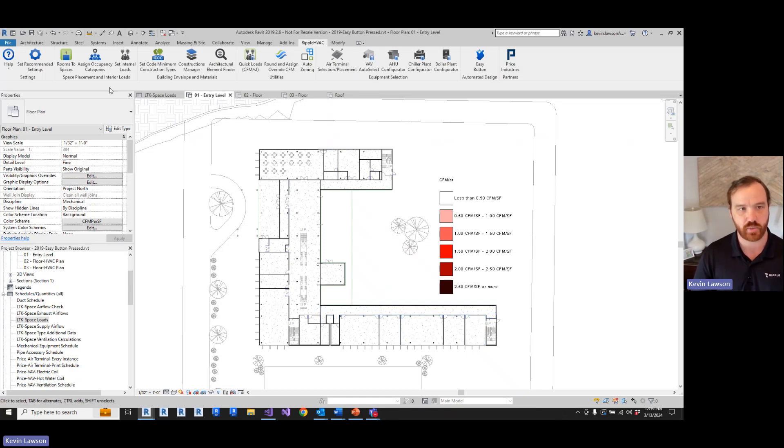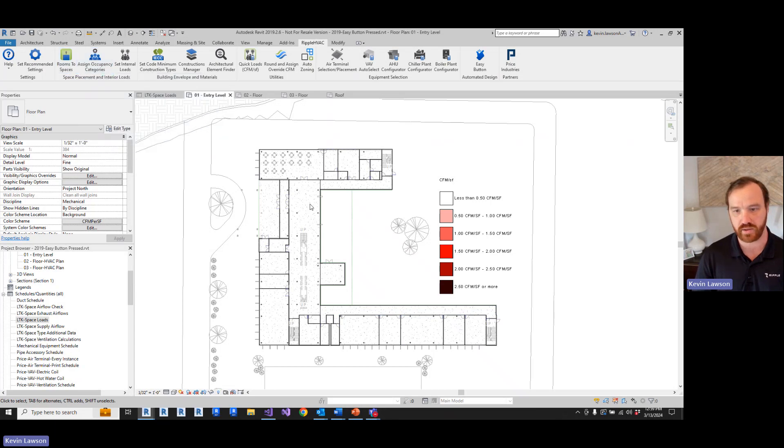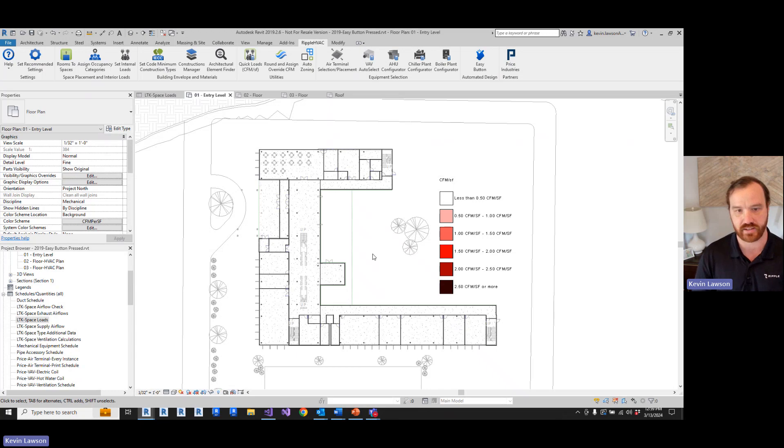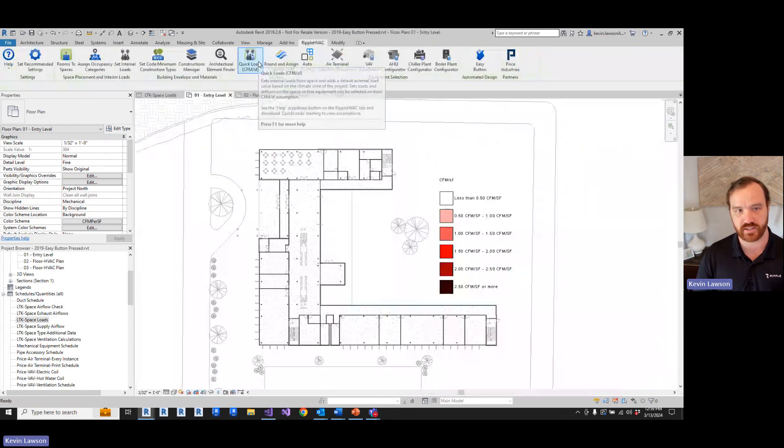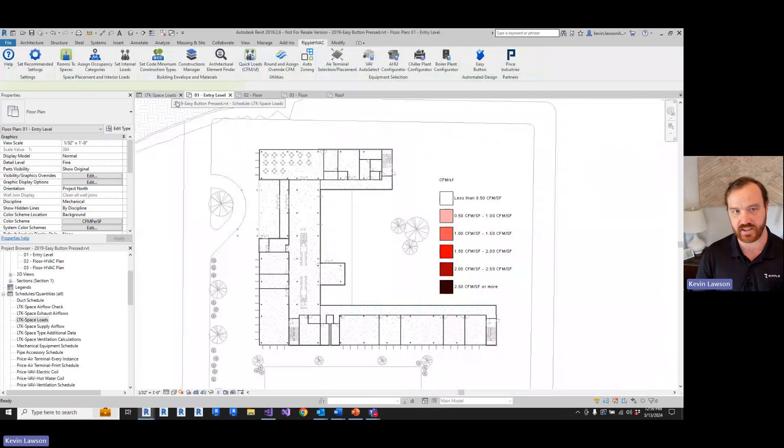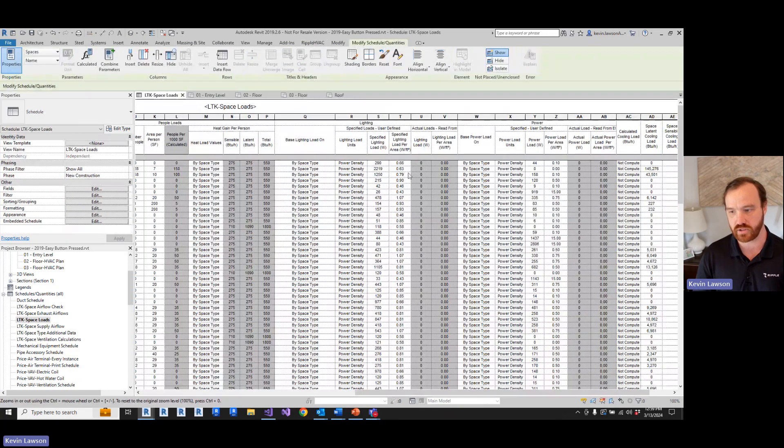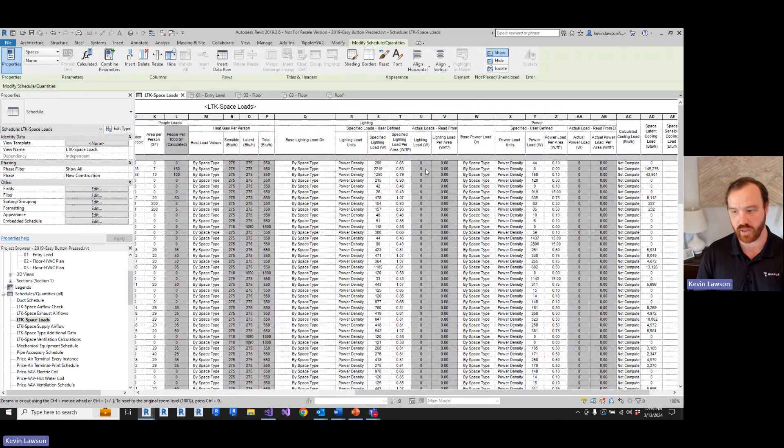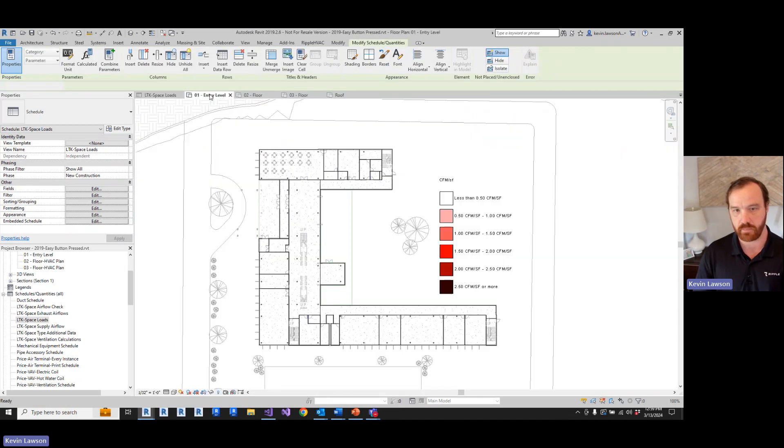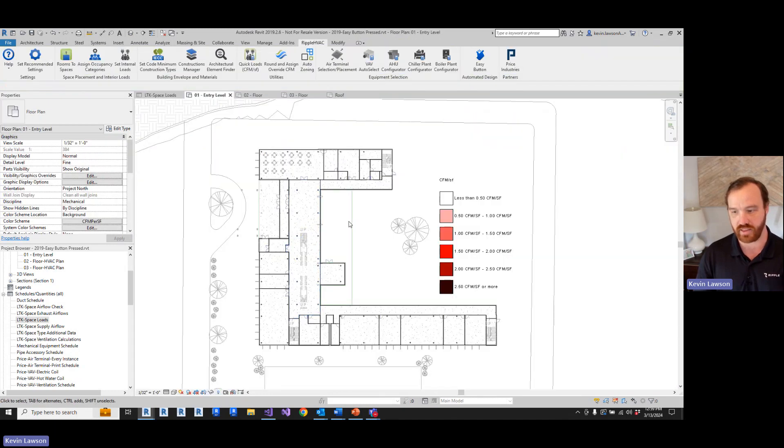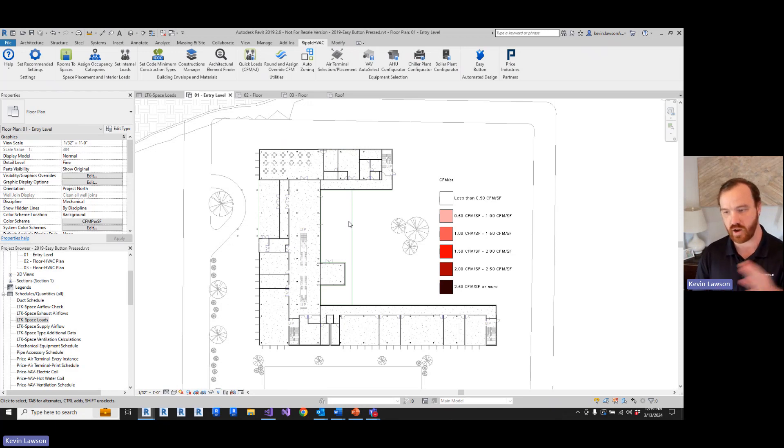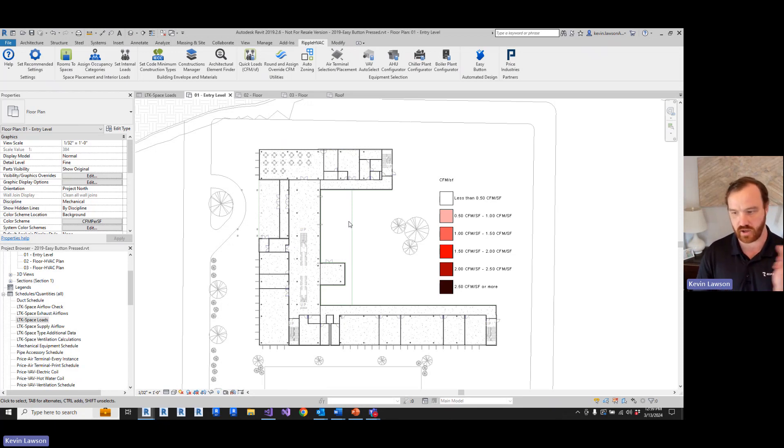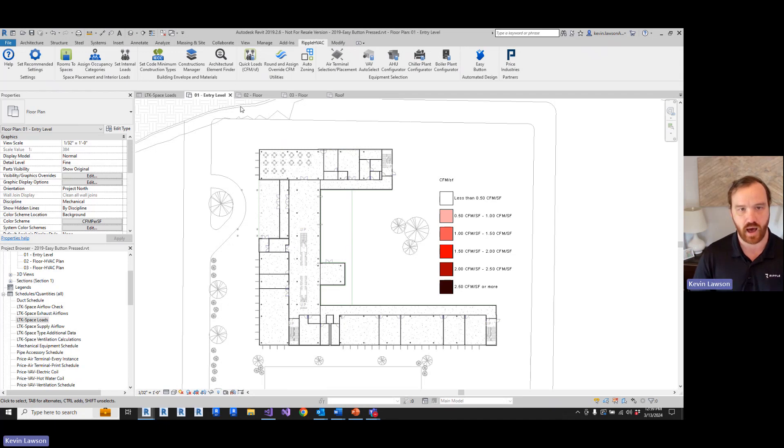But since we can get occupancy categories and areas assigned so quickly, we can get a little bit more granular on how we assign CFM per square foot. What the quick loads tool is gonna do is take these internal loads and add a rule of thumb external envelope load factor based on the climate zone of the project.